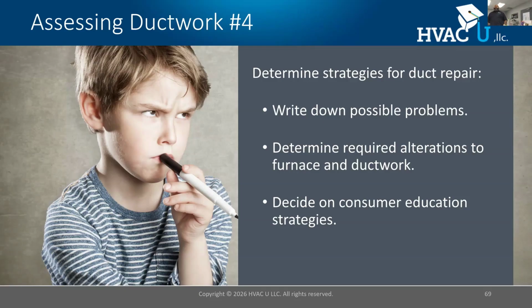Sure. For the pressure pan test, the ducts are connected to the building shell. They should be at the same temperature and pressure as the building shell when they're in service. If they're outside the thermal pressure boundary, they should still be at the pressure inside the building shell. So what the pressure pan test does is help you determine whether the shell is leaking through the duct system. First things first, the blower door has to be running. When the blower door is running, it makes a 50 pascals test pressure difference. I'm going to use that reference point to check across the thermal pressure boundary, that drywall. And it's letting me know, are the ducts leaking through the building shell? Do I have some type of communication? I want the shell and the duct system to be pretty close to zero. If I have something significantly greater, like close to 50, that means the ducts are relatively connected to outside. So that's that part of it.